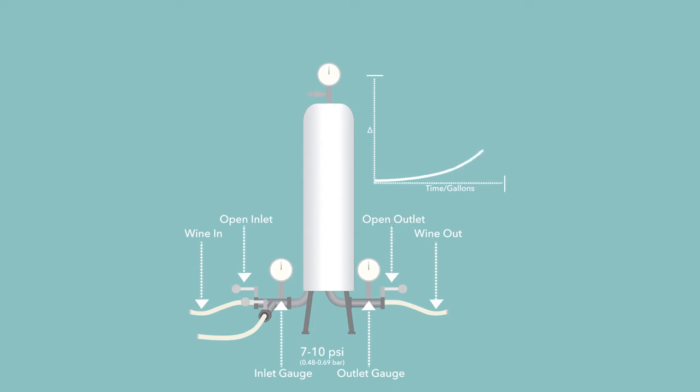Graphically, this is seen as an exponential growth in pressure. As time passes and gallons are filtered, pressure will increase at an accelerated rate. If regeneration of media is desired, such regeneration should be done prior to the knee of the curve or 45 degree tangent.